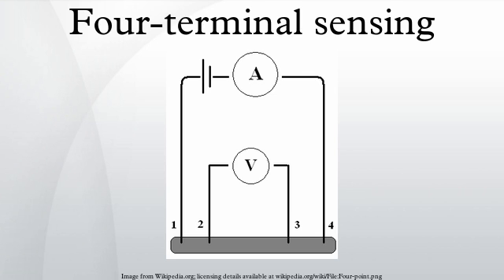The technique is commonly used in low-voltage power supplies, where it is called remote sensing, to measure the voltage delivered to the load independent of the voltage drop in the supply wires. It is common to provide four-wire connections to current sensing shunt resistors of low resistance operating at high current.